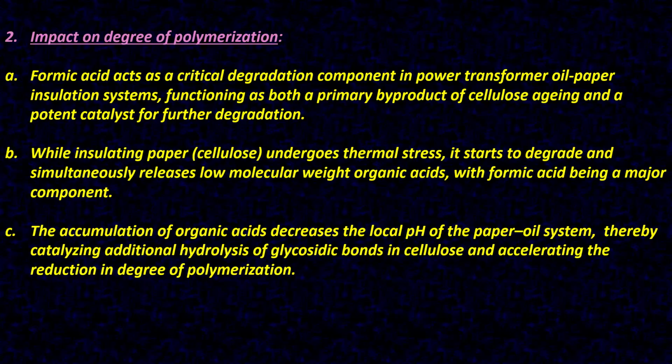The accumulation of organic acids decreases the local pH value of the paper oil system, thereby catalyzing additional hydrolysis of glycosidic bonds in cellulose and accelerating the reduction in degree of polymerization.